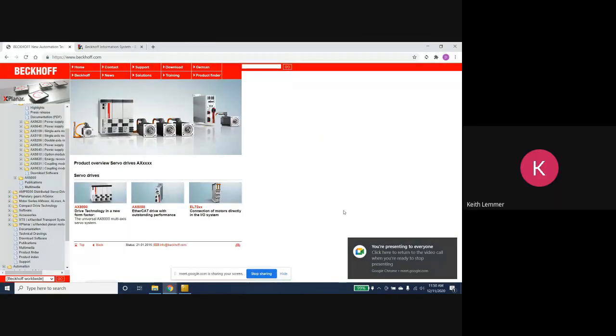So also on some of the installs with commissioning, just for testing, we basically overrode the STO through supplying 24 volt, and then just use that jog feature. And there's some nice jog to and fro, but strictly for testing. You don't want to release it at all to customers like that.